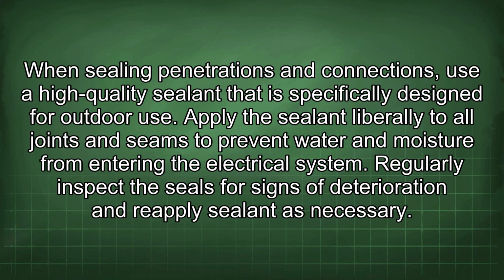When sealing penetrations and connections, use a high-quality sealant that is specifically designed for outdoor use. Apply the sealant liberally to all joints and seams to prevent water and moisture from entering the electrical system. Regularly inspect the seals for signs of deterioration and reapply sealant as necessary.